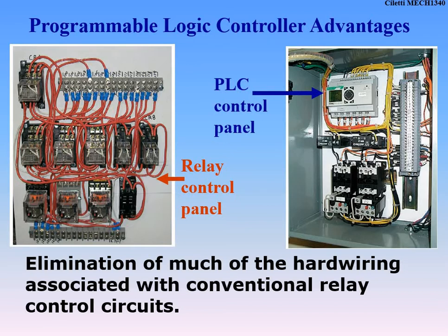It's much more cost effective to use a PLC. Even though some PLCs are very expensive — our Siemens 1500s are very expensive — versus a Siemens Logo or a Siemens 1200, which aren't quite as expensive but their functionality isn't as good. Relay control takes a lot of wiring just for basic controls. Essentially, PLCs were there to get rid of relay logic. But relay control panels still exist — if there's only a few IOs, it sometimes makes more sense to do relay control because PLCs can get pricey.